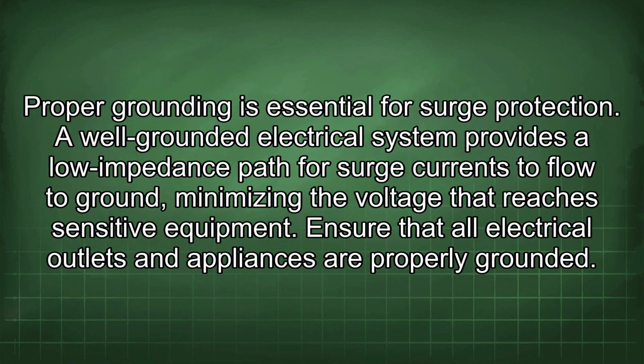Proper grounding is essential for surge protection. A well-grounded electrical system provides a low-impedance path for surge currents to flow to ground, minimizing the voltage that reaches sensitive equipment. Ensure that all electrical outlets and appliances are properly grounded.